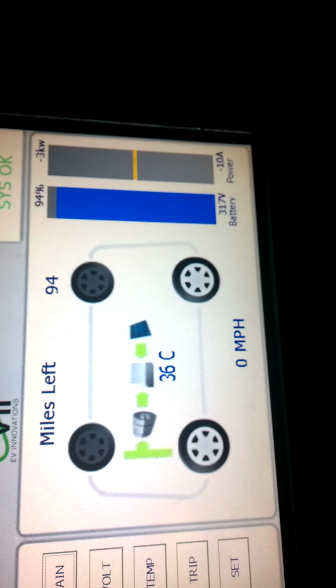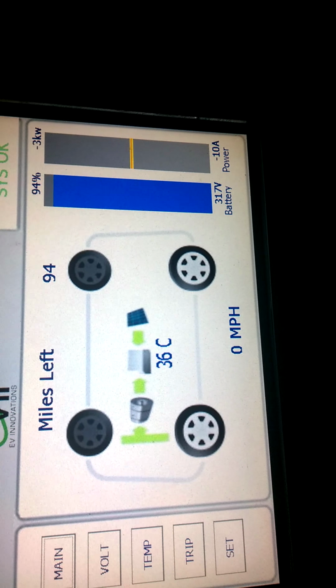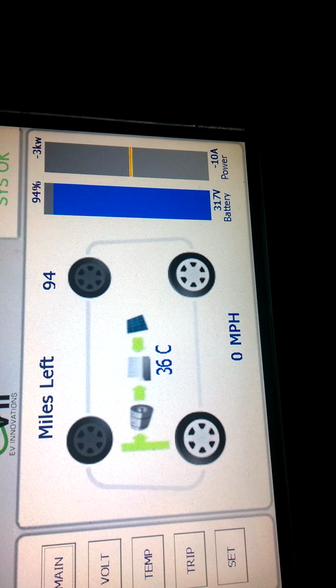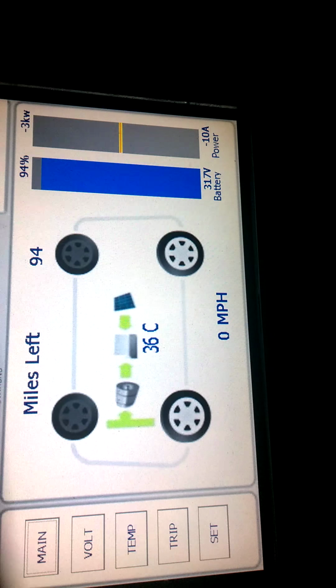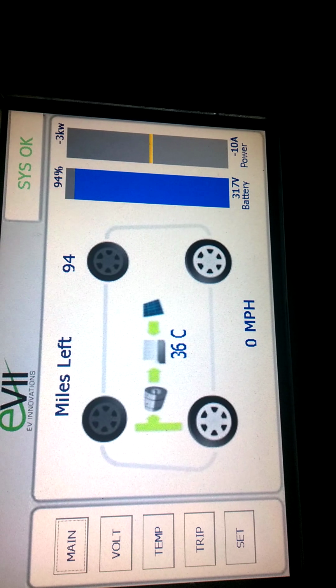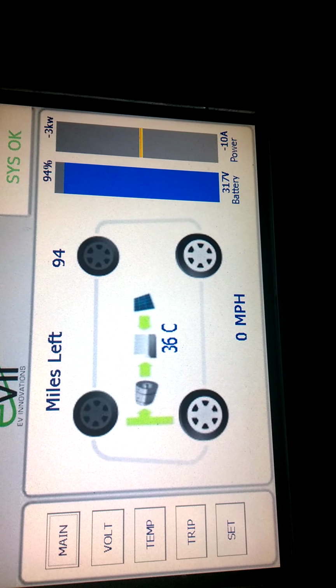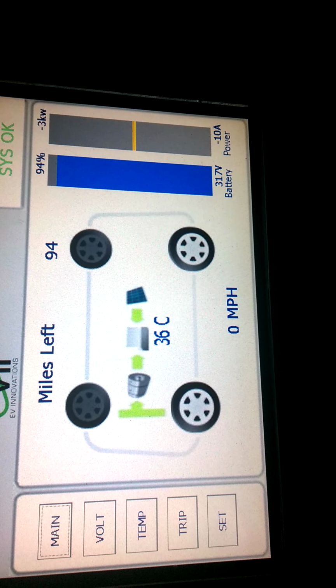Like if the current, when you're plugged in, it says 3 kilowatts, that's pretty accurate. You've got a 3.3 kilowatt charger in here. 3 kilowatts, it doesn't have precision to the 10th, so it's probably right about 3.3. Negative 10, 10 amps at 317 volts tells you it's right about 3.2, which is pretty darn close, and it's bouncing between 10 and 11, so it's probably right there.